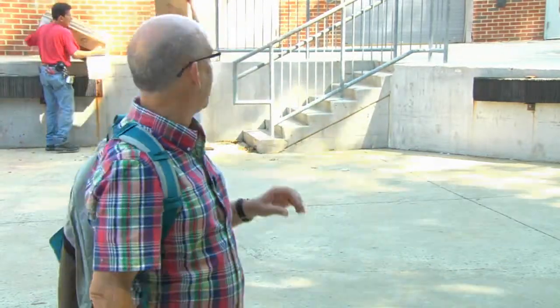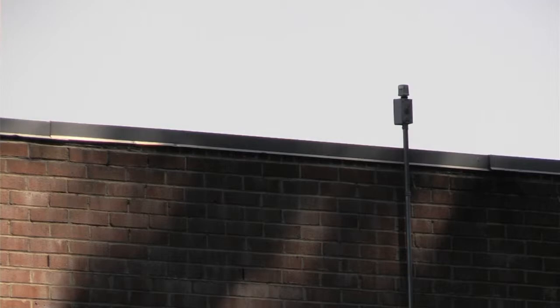If I turn around and look up here, you can see there's a photo cell right up on the top edge of the roof. Now, don't confuse the security cameras on the corners and right here with the photo cell. Why do I want to highlight the photo cell? I think we already know why. Because if it's dirty, if it's not calibrated properly, I need to know where it's at. And does it control all the outside lights? Is there more than one photo cell on this building? How is it connected? I might have to go look at the electrical prints at this point, grab an electrician, but I want to make sure the photo cell is working properly. I need to know where it's at.